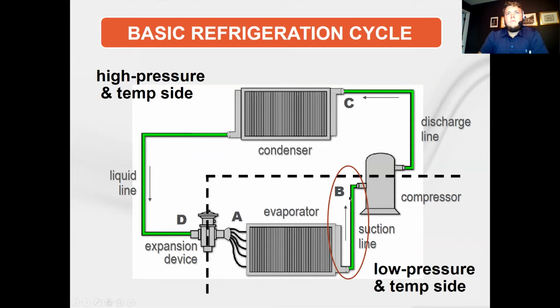There's a thermal bulb that attaches at point B and a pressure tap that attaches at point B. And that tells the expansion device how much superheat, meaning how much you are above the saturated temperature. So it senses the pressure of the line, senses the temperature of the line. You want to make sure you've got 10 to 15 degrees of superheat in that gas so that there's no liquid making its way back to the compressor. So thanks, Marty, for adding that to your question there.